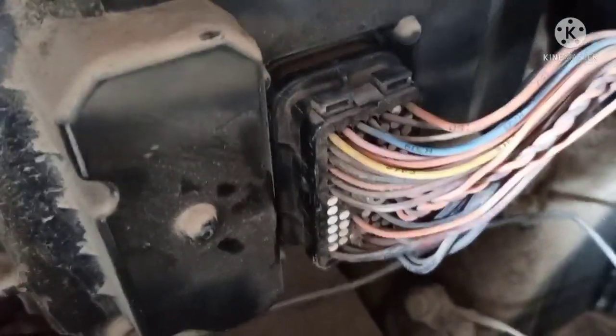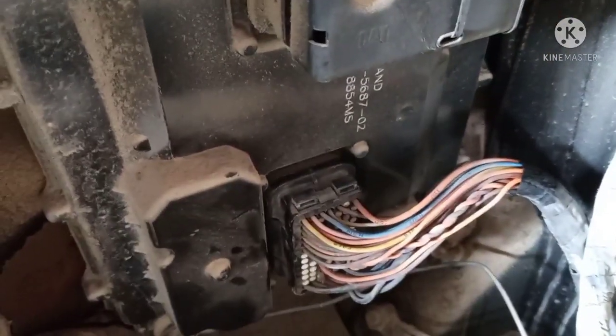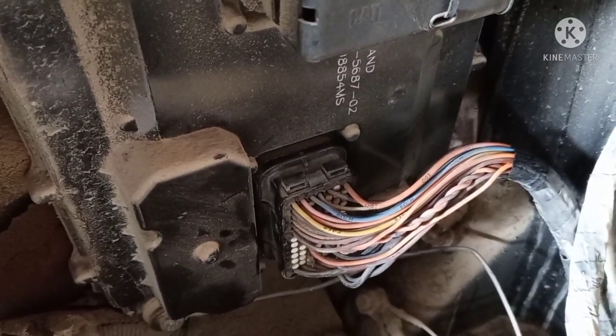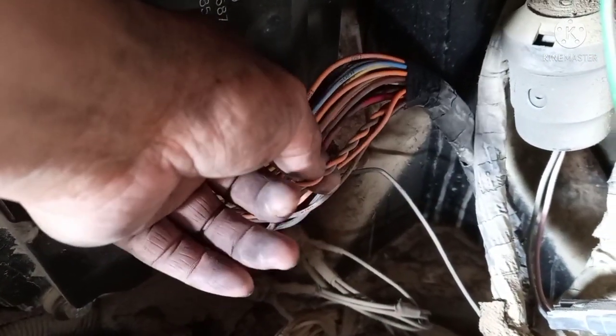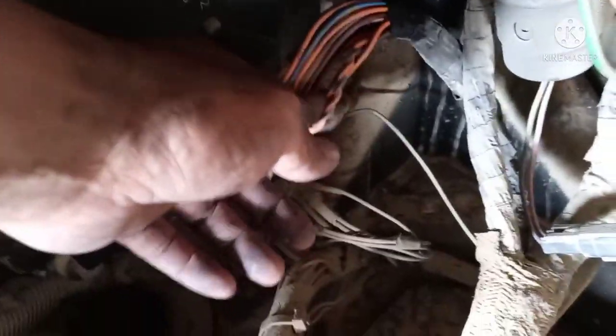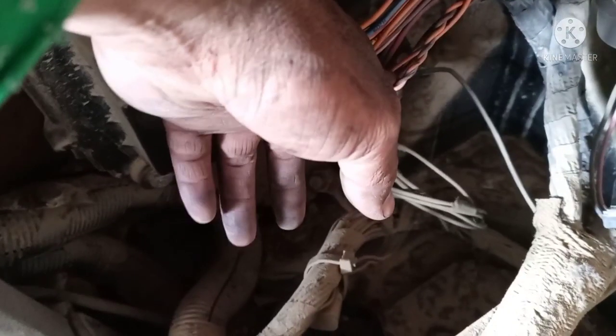Now I will show you something. This is the rear side of the operator seat. I have tried already this ECM. As you can see, this is the ECM, and this is the implement. I'll try to remove the implement socket and then check this wire. This wire is the data link. The orange color is the data link positive, and the brown is the data link negative. I'll check it through the ground based on the Caterpillar troubleshooting.